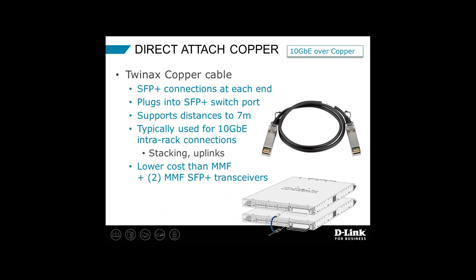I don't want to discount another 10 gig over copper technology called Direct Attach — a lot of people call these DAC (Direct Attach Copper) cables. This is basically a twinax copper cable with SFP+ style connectors at each end. You plug these into your SFP+ switch ports, server ports, or storage ports. This is a very low-cost way to get 10 gig connectivity without spending money on fiber — recognizing that multimode fiber, SFP+ transceivers on each end, and terminating fiber all cost money. If you're going short distances up to roughly seven meters, you can forego the multimode fiber and use Direct Attach copper. We see a lot of DAC used within a rack or from rack to rack as long as distance is limited to seven meters.